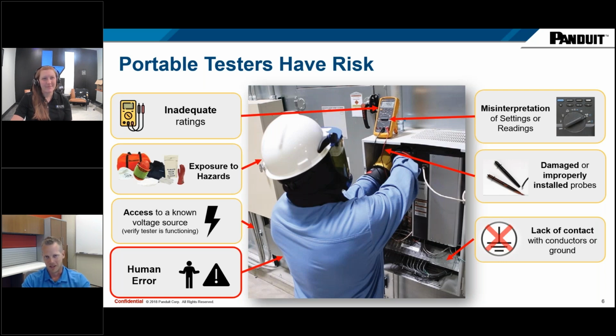And then with the meters, you've also got misinterpreted settings. Again, that's more of a human error. Potentially you're misreading it. The probes can be damaged, and you're supposed to be inspecting those, but they can still get damaged, and that's another thing to worry about. And then lack of contact, which Caitlyn touched on earlier as well, right? Those safeguards, touch safe things, which is all awesome. They're there for a purpose, for that incidental contact. But when you need to make contact, they prevent that, and they create an additional step that you have to work around.